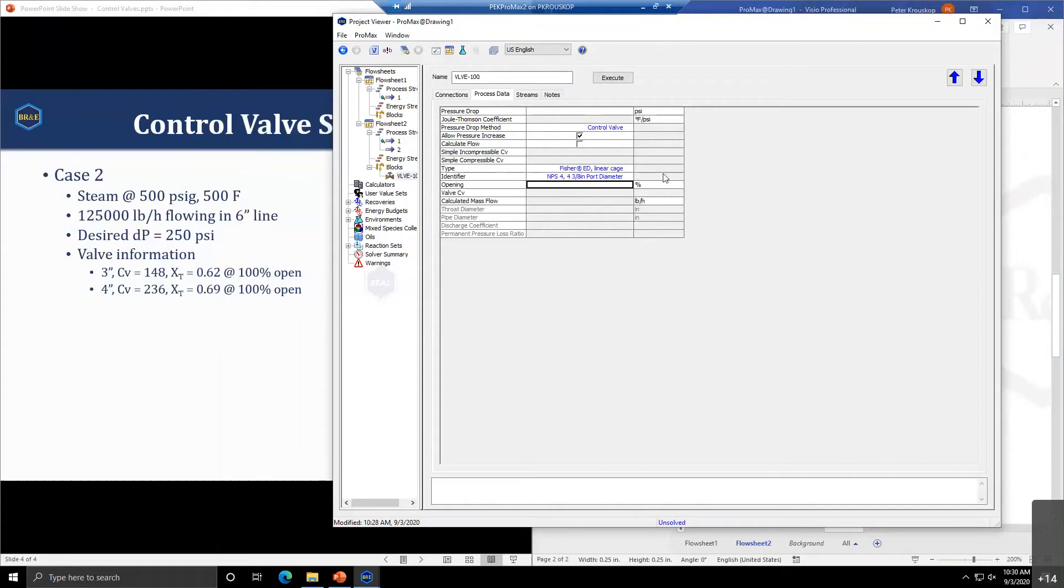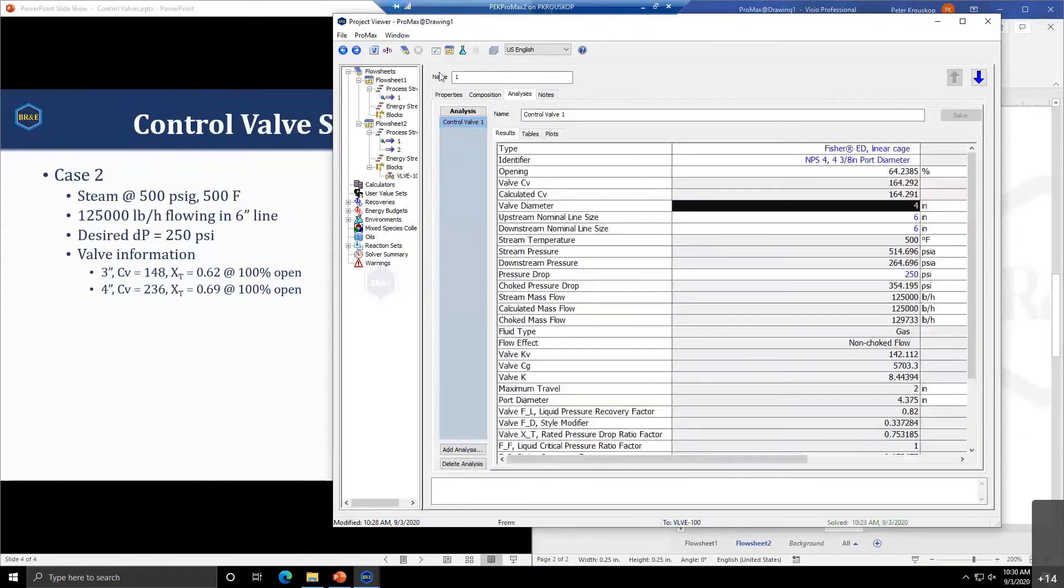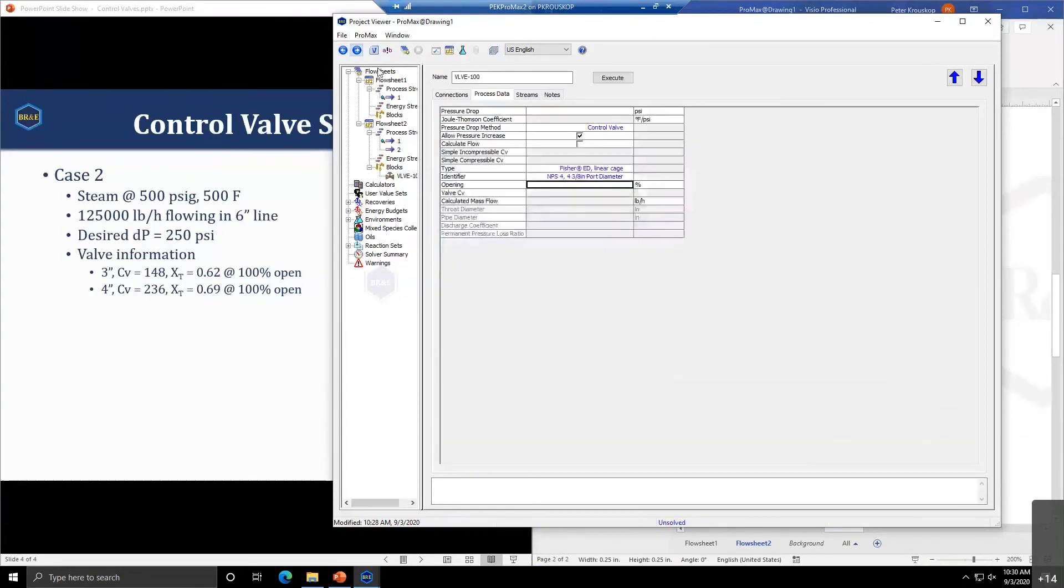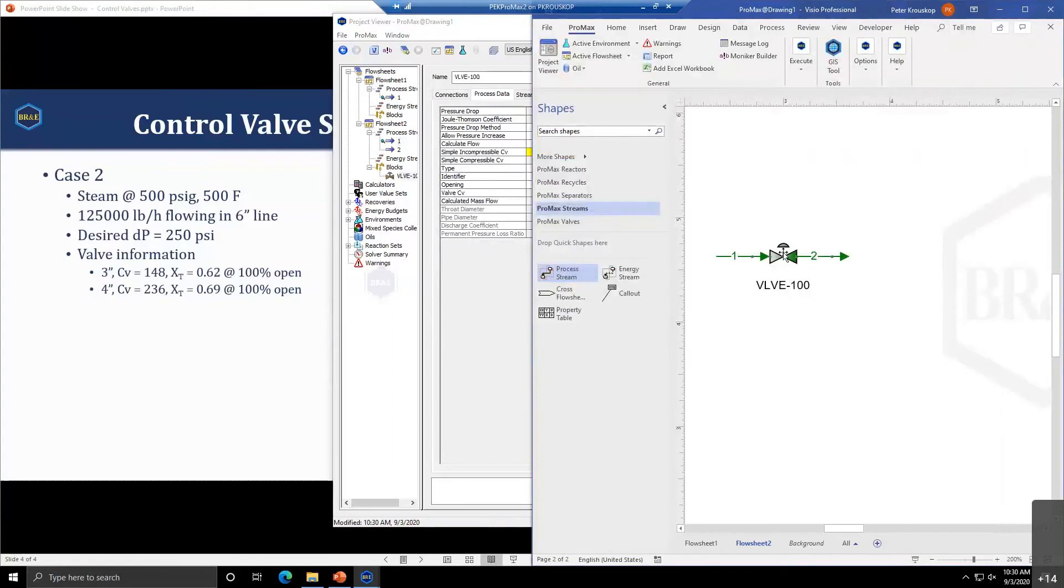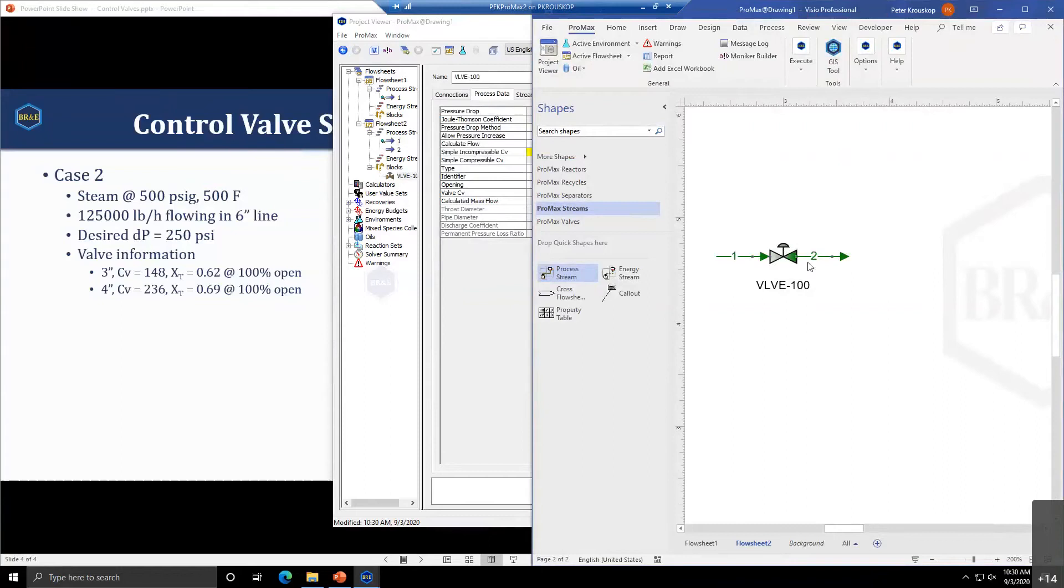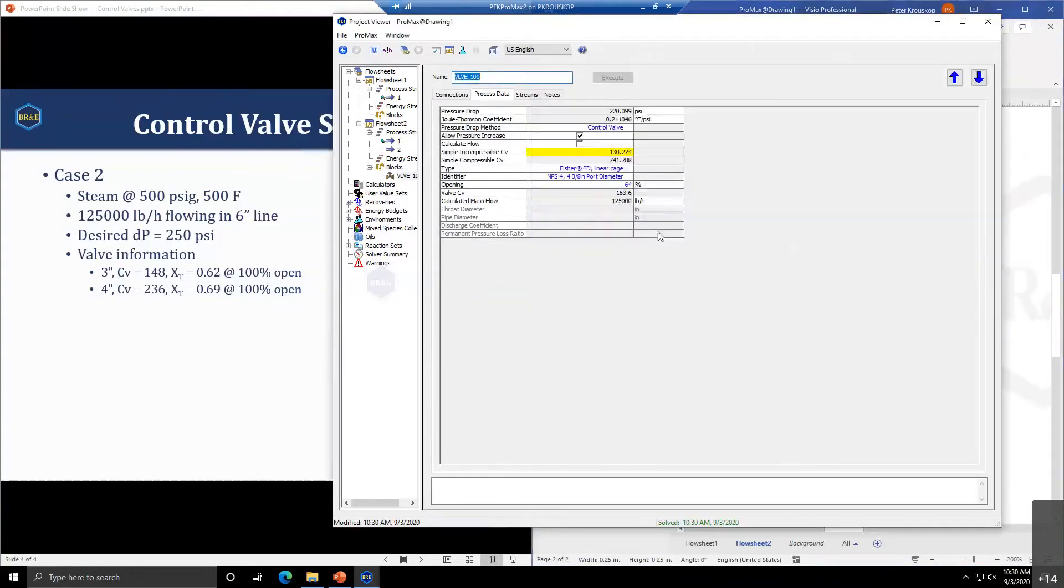If that's something that would be very useful, please let us know and we can get it added in. If we model this at about 64% open, ProMax will calculate the pressure drop for me. At 64% open, I have a 220 psi pressure drop. The pressure drop is dependent on the flow rate and the CV of the valve, which is determined from the valve data and the percent open you've entered.